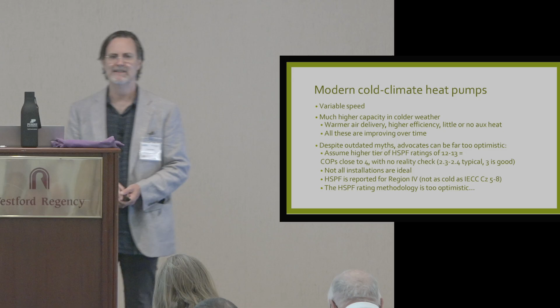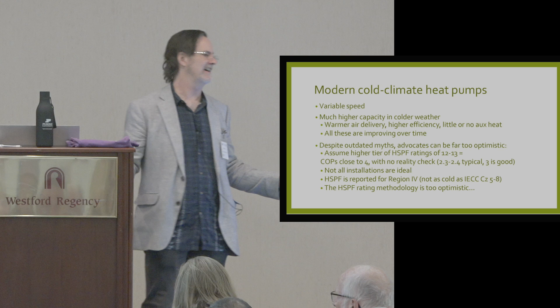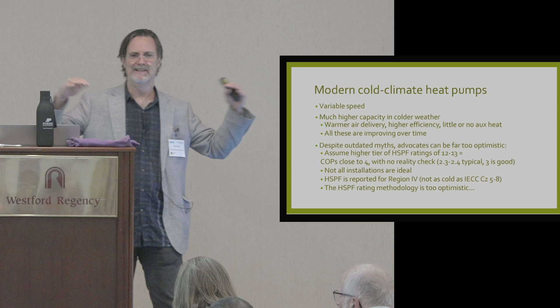Part of the reason is that not all installations are done quite properly. One of the big reasons is that the HSPF values are reported for DOE Region 4, and the region maps for heat pump efficiencies are not the same as the IECC climates. Region 4 is a little colder, actually, than the IECC climate zone 4 that a lot of people here are familiar with, but not a lot colder.